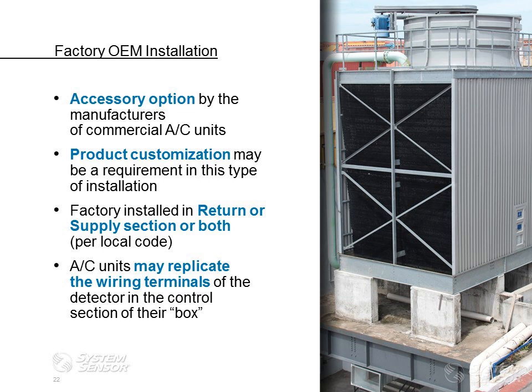Now, the air conditioning units may replicate the wiring terminals of the detector in the control section of their box. Some rooftop manufacturers do this just for ease of installation, that off the production line, they will run the wiring and the wiring harness back into the control cabinet. That basically reduces the need of the contractor, the installer, the service technician to get into the guts of the unit. They can go to the control cabinet and do their wiring there. It's really more for ease of use and installation.